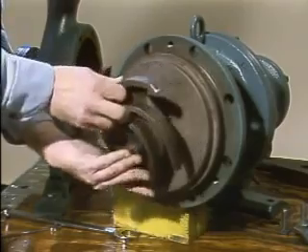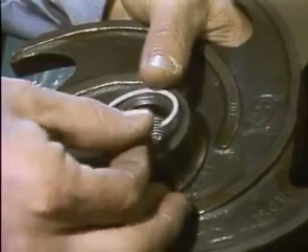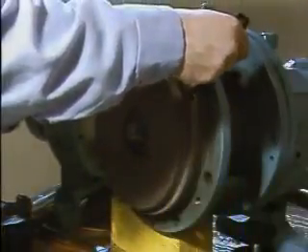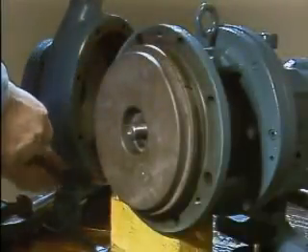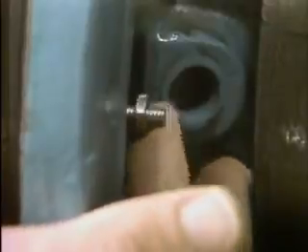Next, the impeller is removed, and so is a small impeller gasket. The backplate is match marked with the frame to make reassembly and alignment of the components easier later on. Then the backplate can be removed.